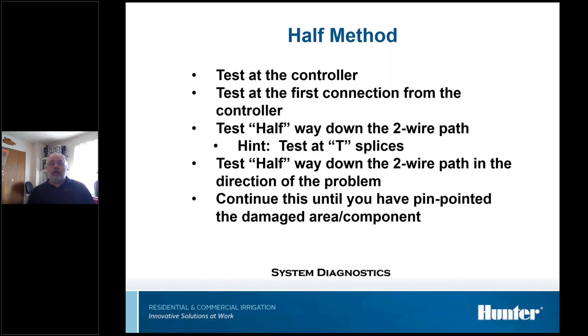This is a messy, dirty, time-consuming method. It does work. We've been doing this for over 20 years. It works. If you don't have a clamp-on amp meter, this is how you'd have to find the severe shorts. We've never found any other method, either the half method or using an amp probe, that works and works consistently. You can go disconnect every controller, go down the wire path one at a time, and it'll take you even longer.